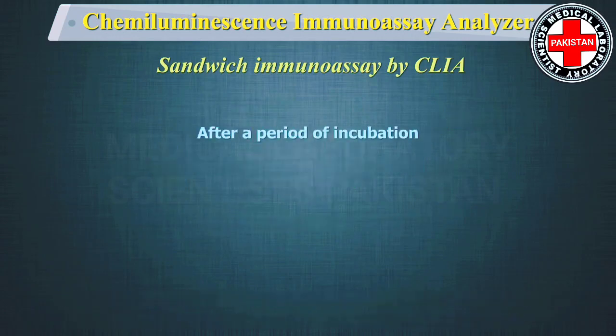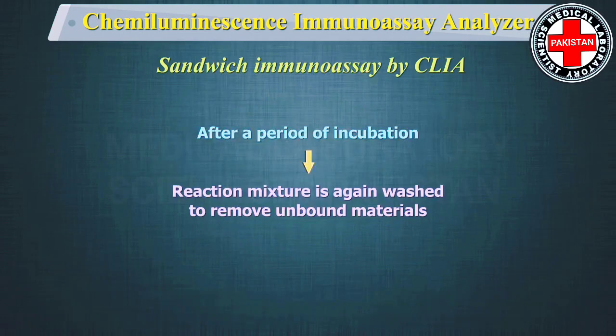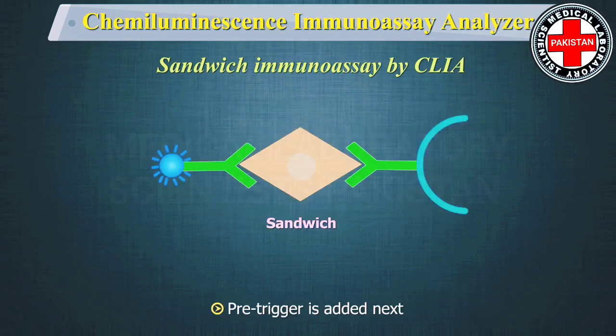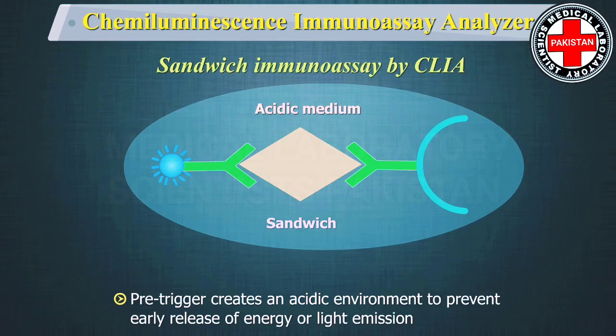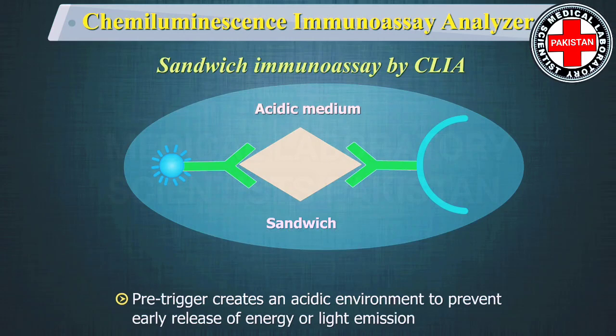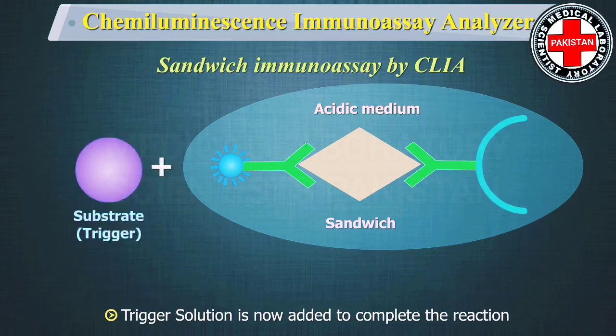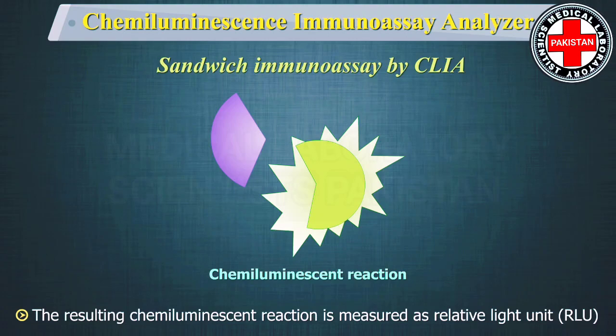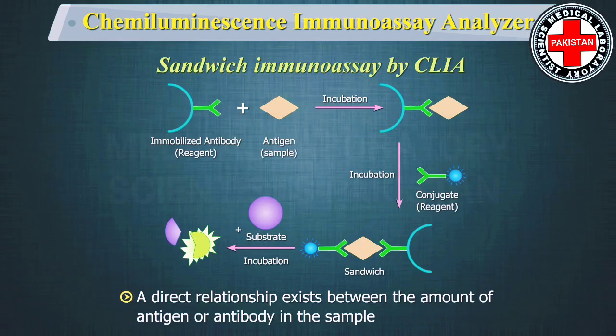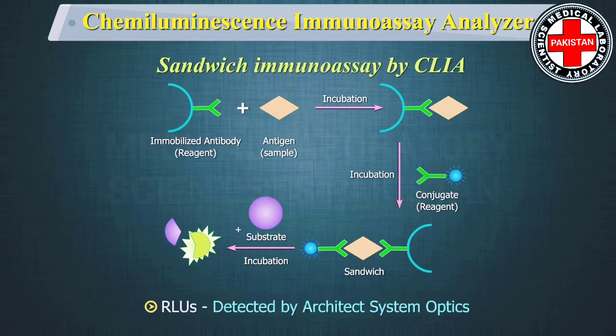After a period of incubation, the reaction mixture is again washed to remove unbound materials. Pre-trigger is added next, which creates an acidic environment to prevent early release of energy or light emission. Trigger solution is then added to complete the reaction. The resulting chemiluminescent reaction is measured as relative light units, and a direct relationship exists between the amount of antigen or antibody in the sample and the relative light units detected by the system optics.